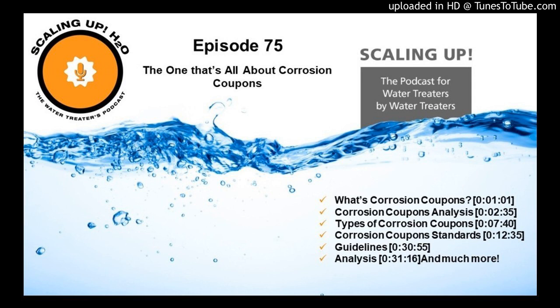So if you want to think of that in these terms, let's say the metal in a heat exchanger is 1/10 of an inch thick. If you have a corrosion rate of 10 mils per year, it's going to take 10 years to penetrate the walls of that heat exchanger. Now, that's not exactly true, and I can throw a bunch of things in there to argue whether that will work or not, but for our definition, that's how we're going to look at it.